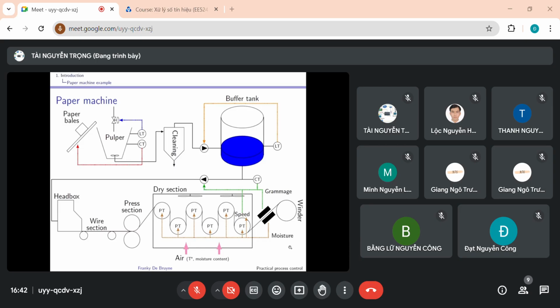So the consistency control loop is shown in red. The consistency of the pulp is measured using this transmitter and controlled by adapting the speed of the conveyor belt. In some cases, the speed of this conveyor belt is fixed, and the conveyor belt is either running or it is not running, and then you're in the off state. What the controller should provide is the on-off sequence to the conveyor belt. This type of control will require PWM, pulse width modulation. This should ring a bell because this is a concept that we've seen in other courses. And this type of control is covered in section 6 on digital MVs.